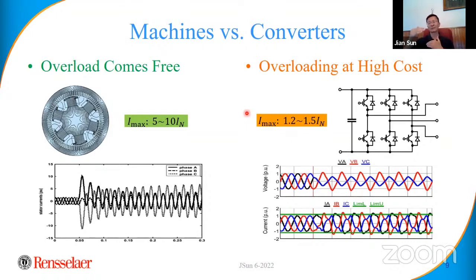Maybe 50% overcurrent. And if the actual current exceeds that, it's not a problem for the semiconductor device, because the device can shut down in microseconds, right? It will protect itself. It just simply shuts down. The current will stop, right? And that's an advantage compared to generators, because a generator cannot stop that. Converters can stop it. That's fine for the converters, but it's going to be really problematic for the system, because today's system relies on the fault current to clear the fault, and to support the system during the fault. If we have all converters operating the system, and you get some fault somewhere, a glitch, all the converters start to trip. Then you're going to have a blackout every day, because all the converters just trip, right? And you have to restart, okay? That's certainly not possible.